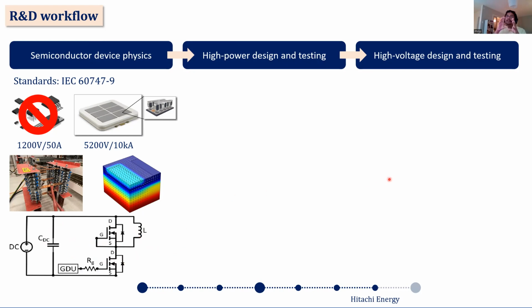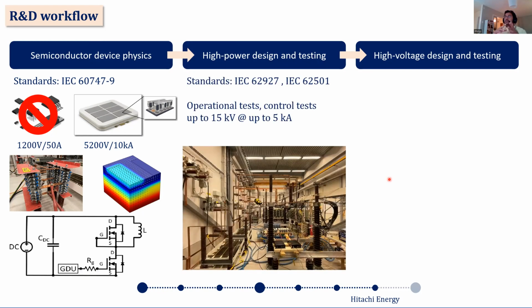But then once I have the semiconductors tested and optimized, I then move on to the converter side. So we then build up these converters. This test can happen at, let's say, a few kV. It can go maybe up to 4 kV, and it can go up to 10 kiloamps. And then we go into the high power testing, which is essentially testing the entire converter. And this can go very high. You can have 15 kV, up to 5 kiloamps or even higher. It can go sometimes even to 8 or 10 kiloamps. So it's a massive amount of power.